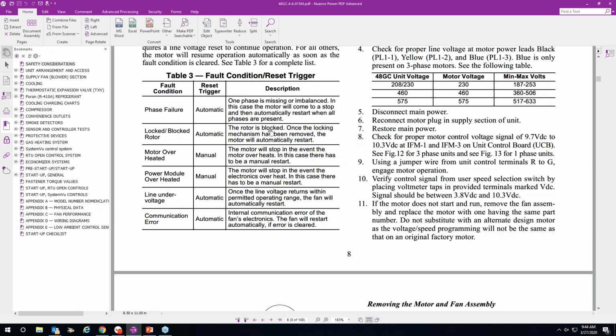The other thing that we run into is on the 208, 230 grids. So there are multiple power grids out there that supply 208, 230 volt. There's Delta power, there's Y power, WYE. We're talking 3-phase now. So if we took our meter and measured L1 to ground, L2 to ground, and L3 to ground on Y power on a 230 volt system, L1 to ground would be somewhere around 120, L2 to ground would be somewhere around 120, L3 to ground would be somewhere around 120. Y power works beautifully on VFDs, and works beautifully on this ECM motor, on this Vane-Axial assembly.